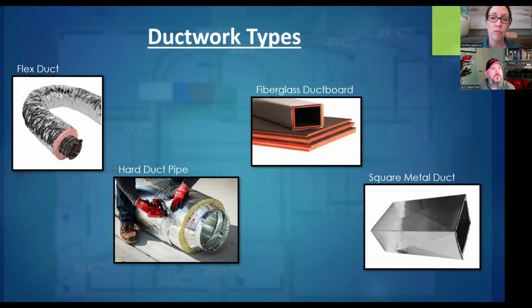Depending on the quality of execution as well—if, for instance, we do an install using all hard pipe, wrapped on the outside, nice, neat, professional, and it's not installed in a very harsh attic, that's a lifetime install; it'll last the life of the house. Take that same system, done properly and executed to a very high level, but put it into a harsh environment like a vented attic exposed to moisture and high heat—it's not going to last as long. It'll have microbial growth, condensation, and so on.